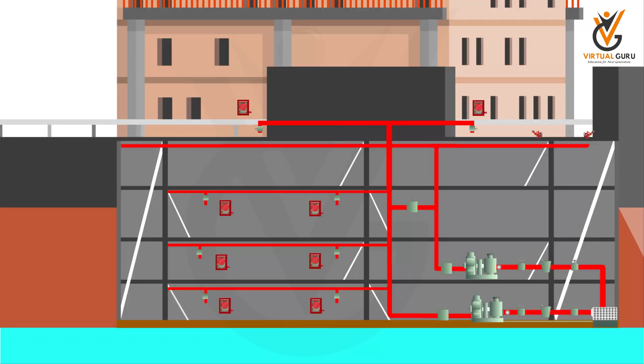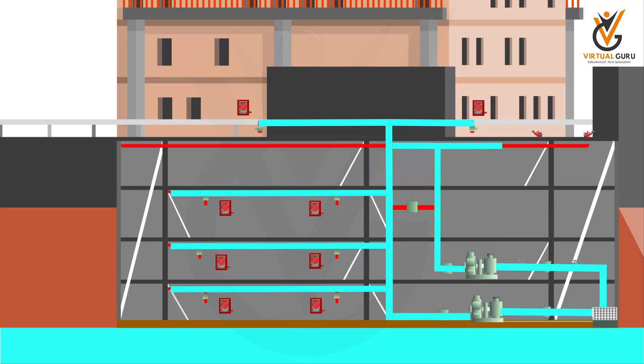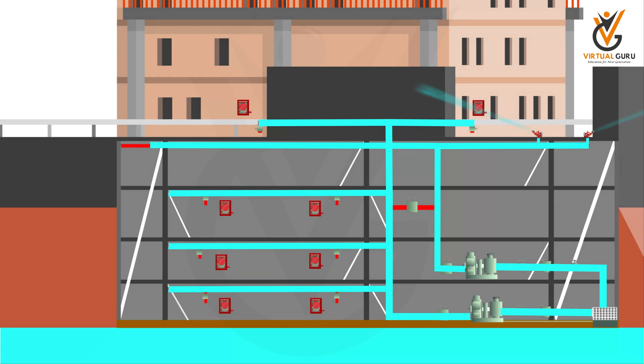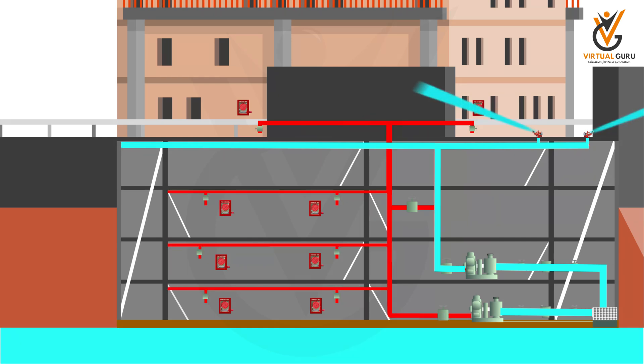We have fire pumps in the engine room. As per regulation, two independent fire pumps should be there, connecting to each other to supply water. The condition is that one pump should be able to supply enough water for two continuous jets to be sprayed.